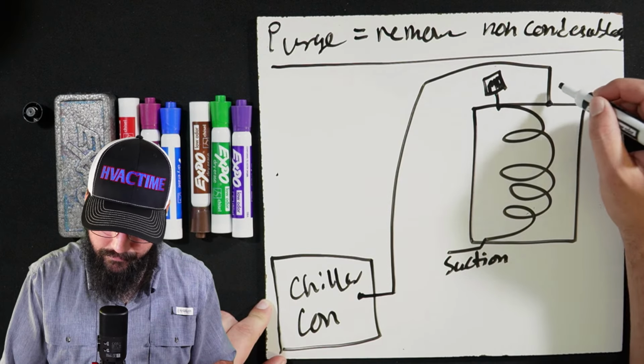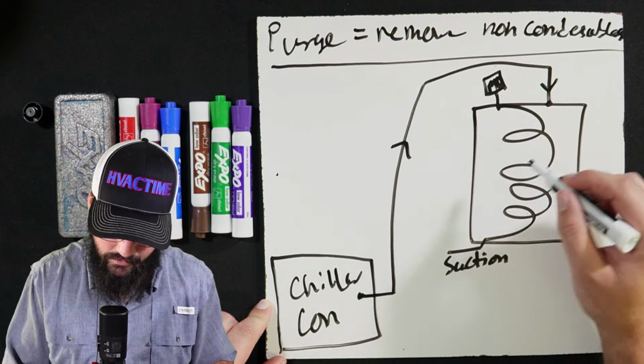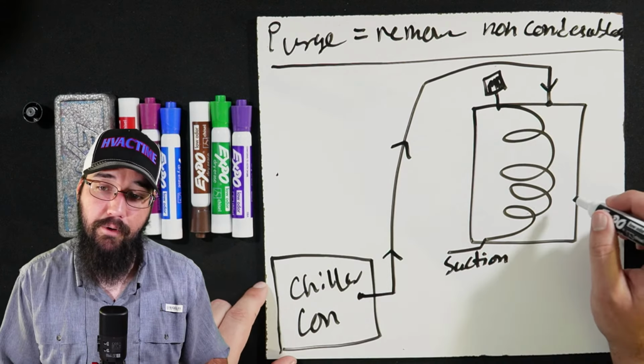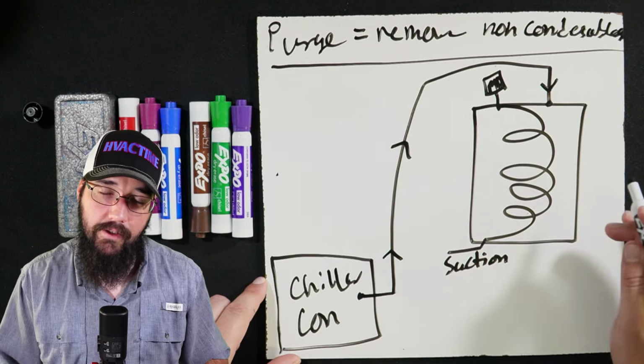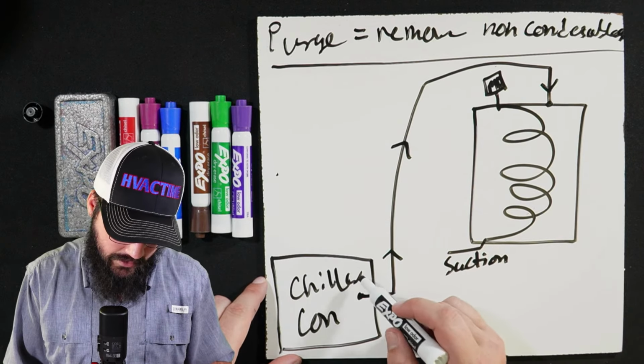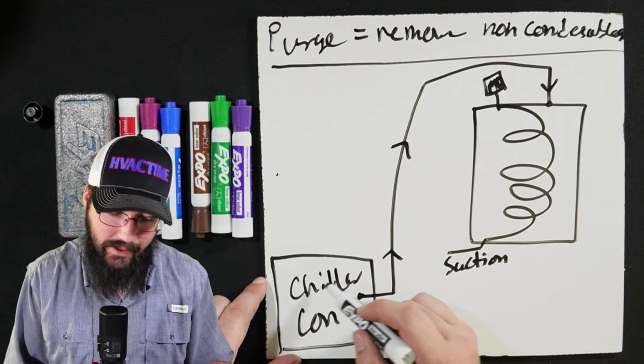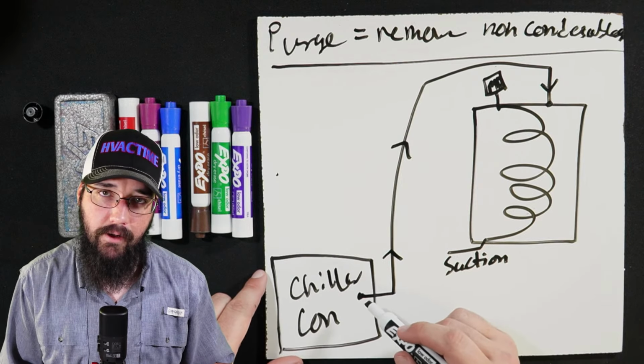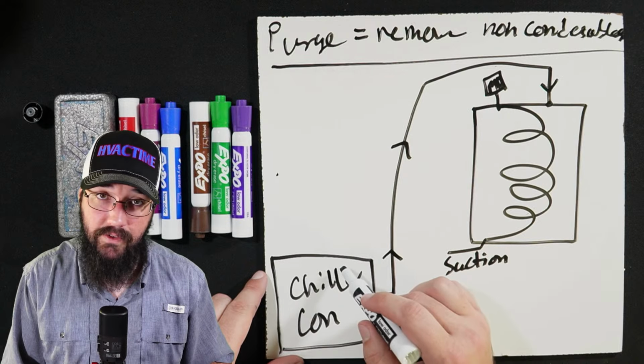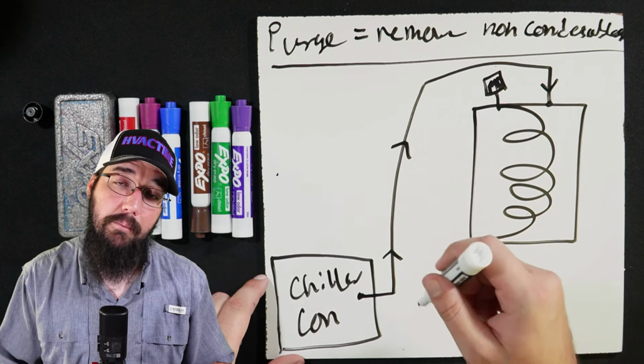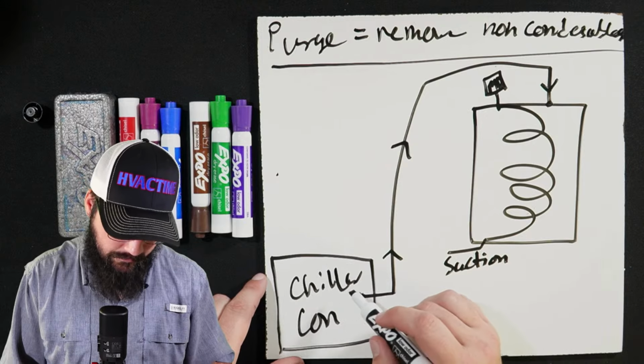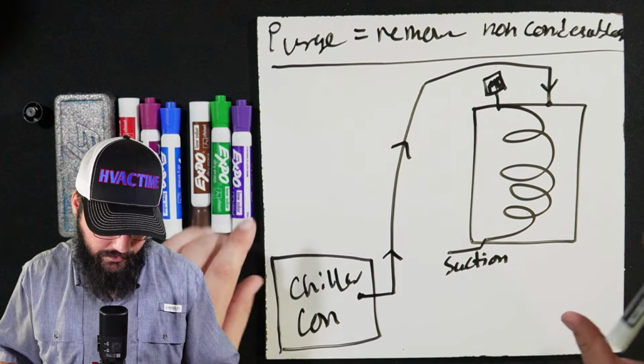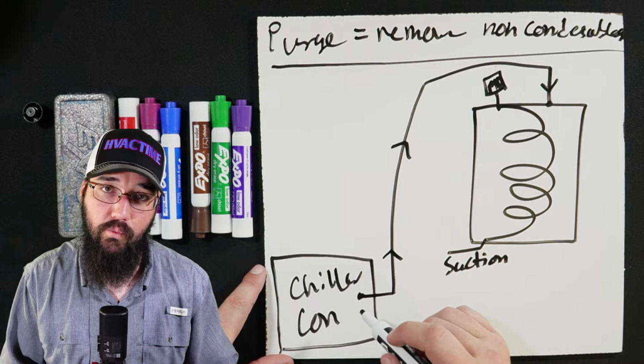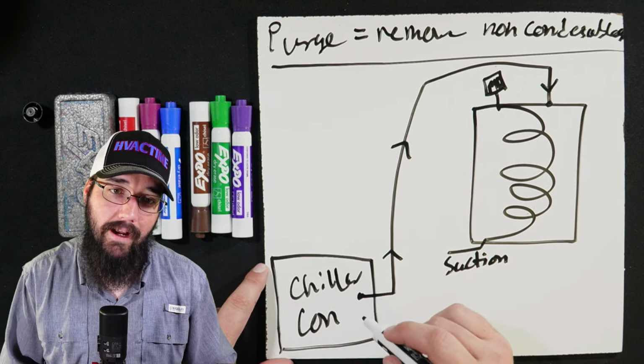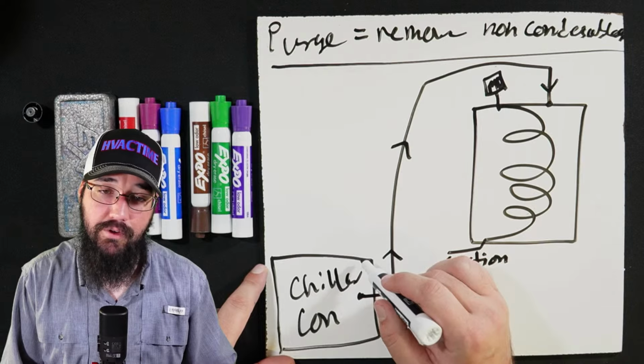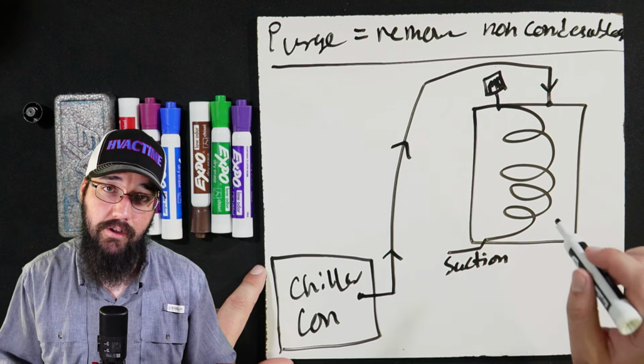this tank. Okay, and I say a midpoint because typically purges are going to run while the machine is online. When the chiller is online, your non-condensables stack about midway in the chiller barrel. They don't stack at the top. They will stack at the top when the machine is off, but not when it is on. Okay, and that's a whole other conversation we could dive into, but just understand where your non-condensables are and why these lines don't connect at the top of the machine. These are meant to run as the machine is running.